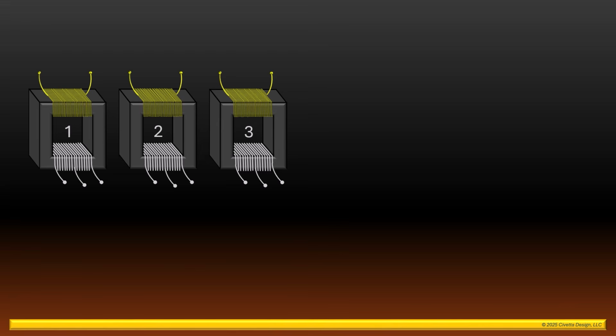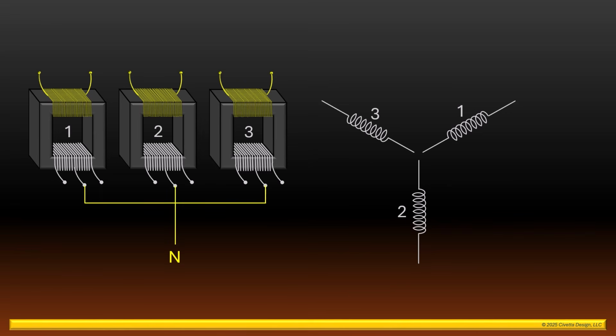To see how this works, we're going to look at just the right half of the secondary winding in transformer number 1. We'll add the same half of the secondary winding in transformer number 2. And then number 3. We're going to connect the center tap of each transformer with a long jumper wire and a lead wire. Shown on the right, this becomes our neutral. We'll then add the X phase lead to the left transformer. And shown on the right, this produces a 120 volt potential between the X phase and the neutral, since this connection is only utilizing half of the winding in the 240 volt transformer.